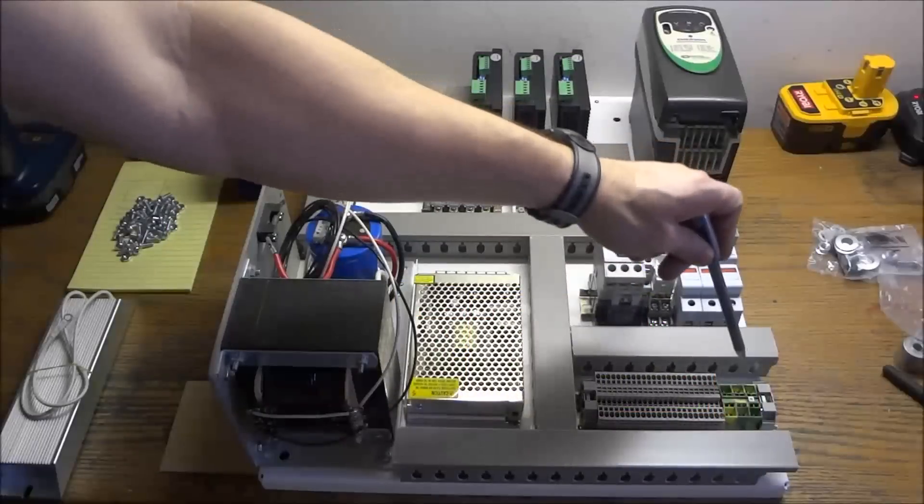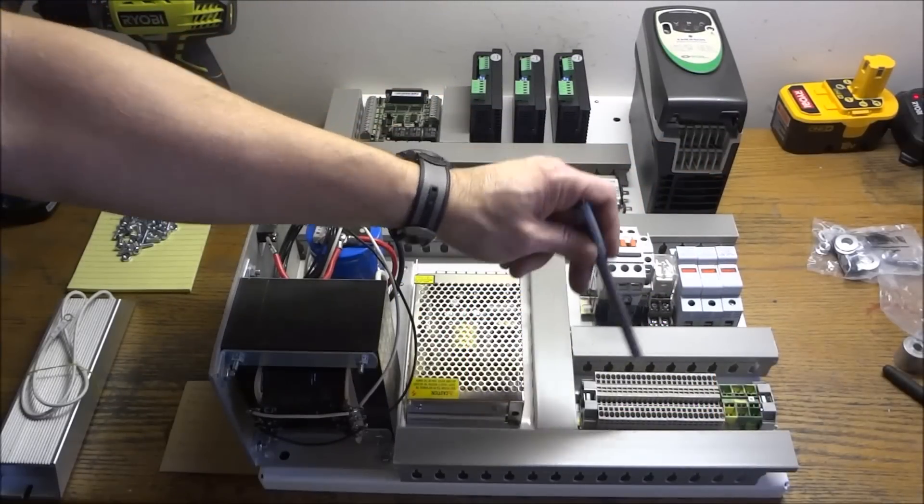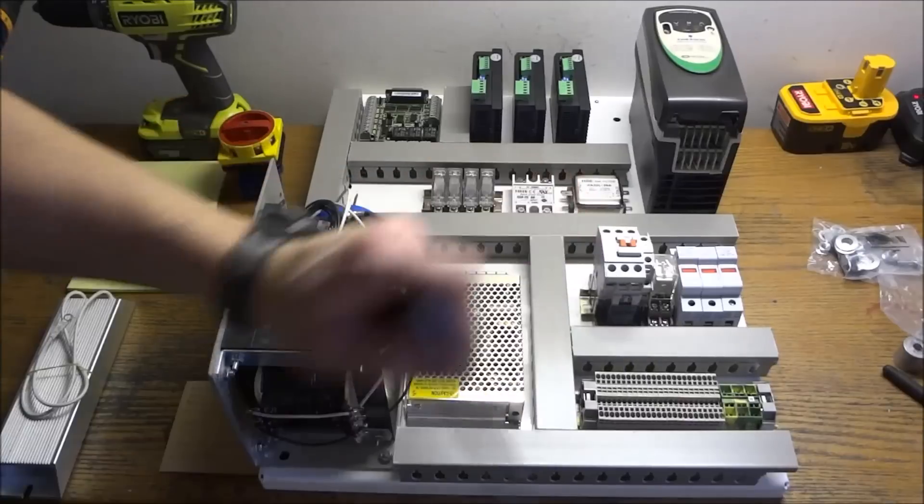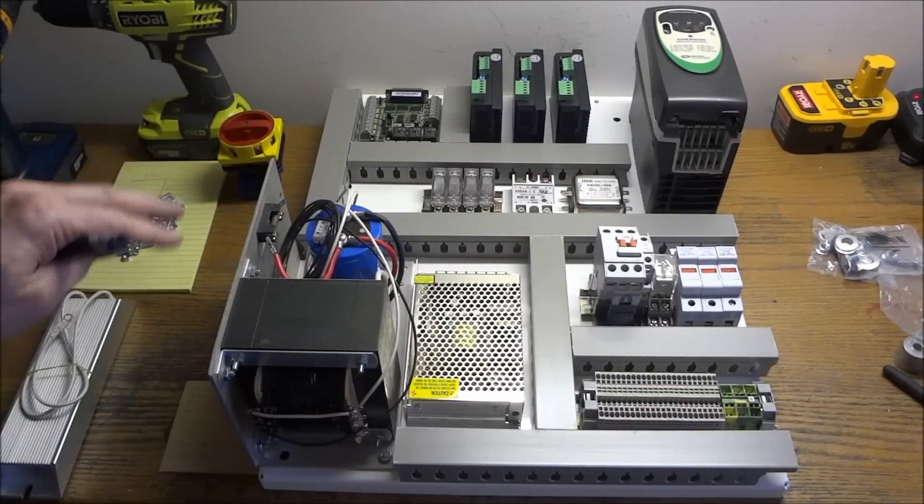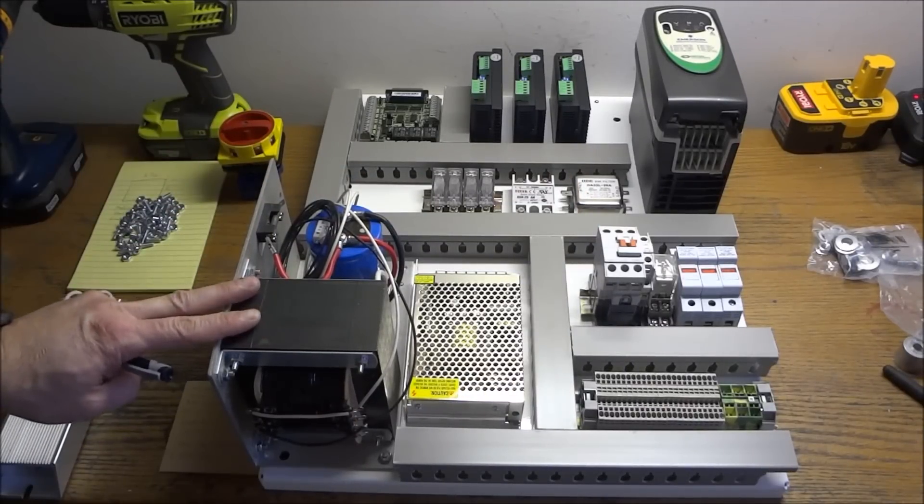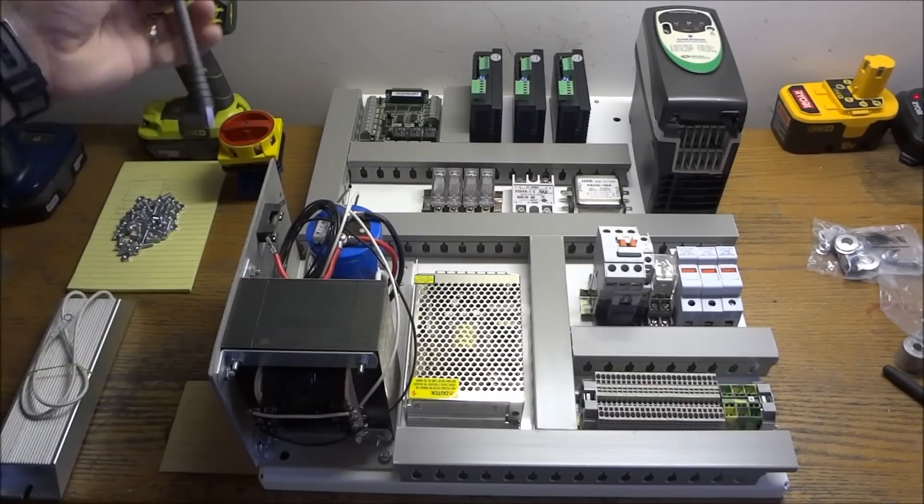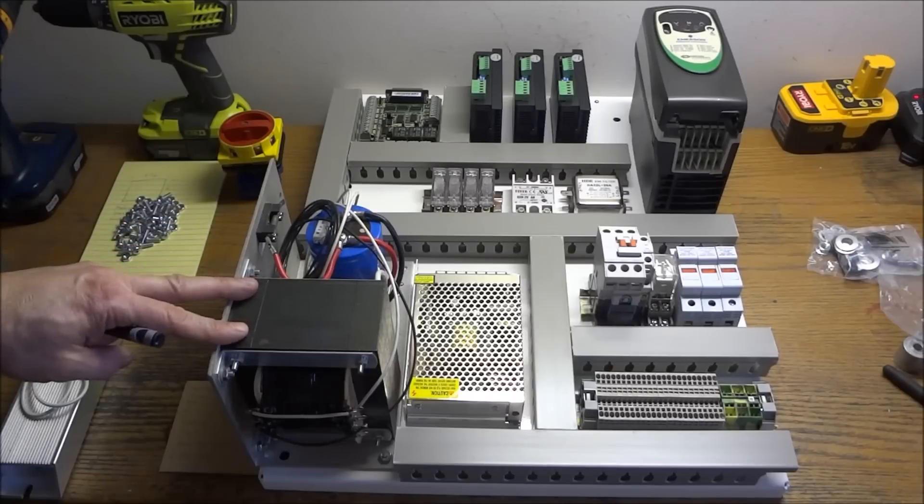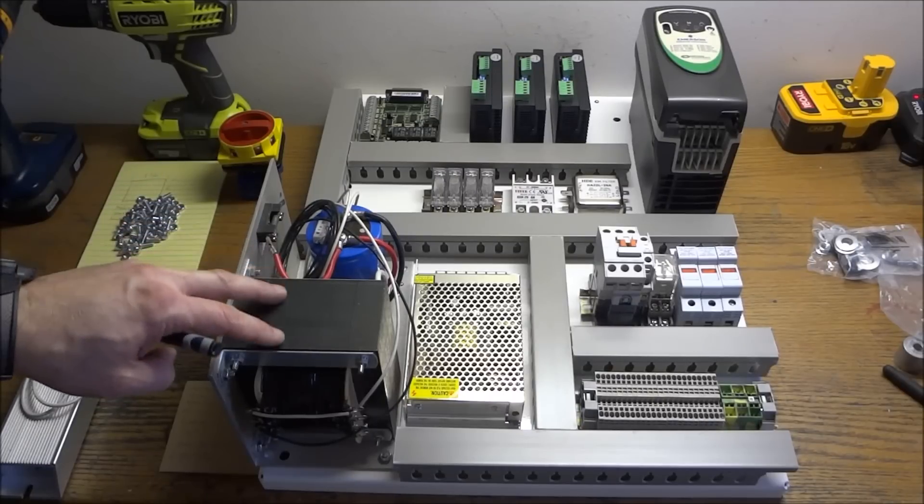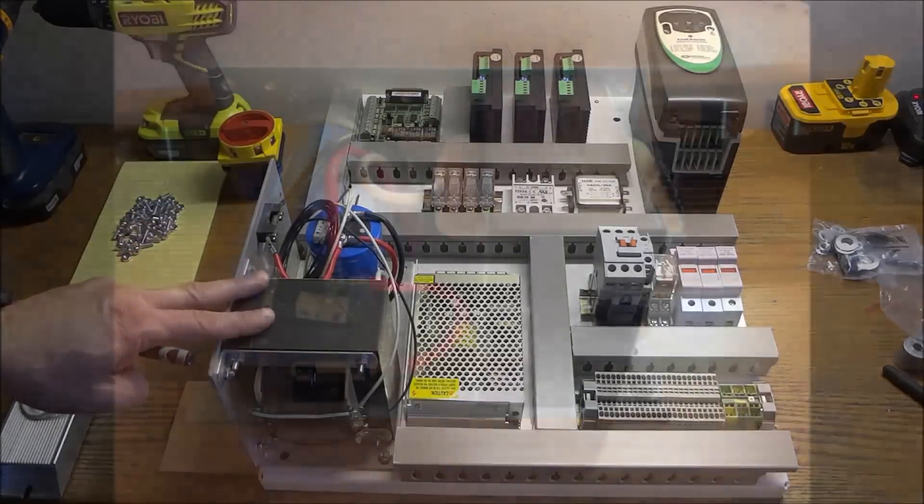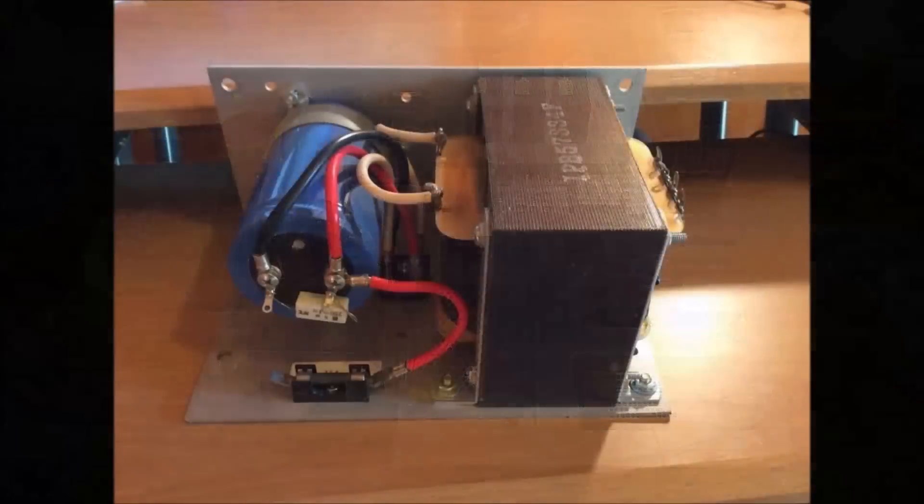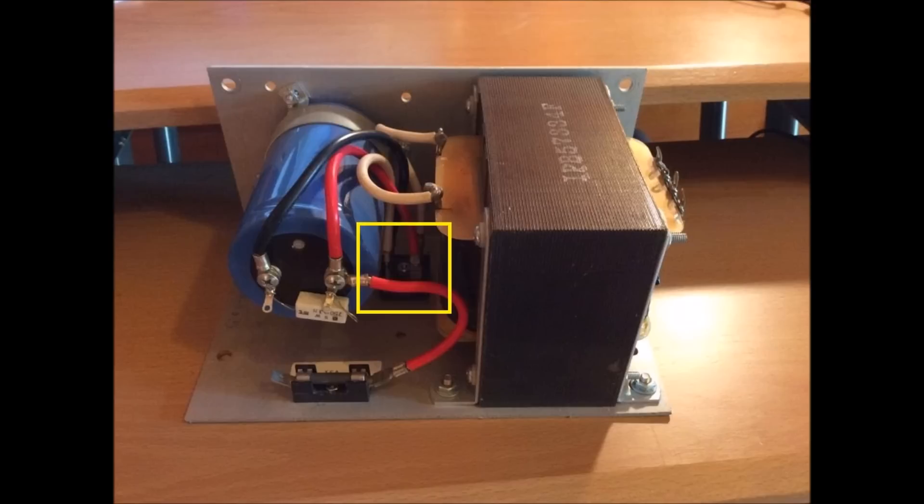We have our terminal strip down here, and this will be where we make all our connections. We have our transformer. Now, this transformer has 110 volts coming in AC and 48 volt AC going out. And if you look right here, the little square item between the transformer and the capacitor, that is a rectifier that converts the 48 volt AC coming out of the transformer into DC.